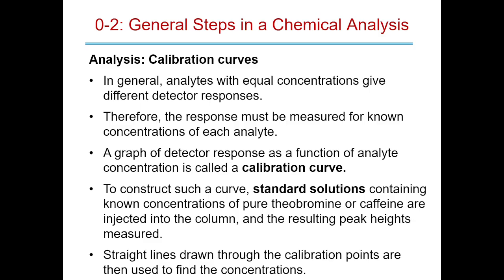By the way, you have to make new calibration curves for each instrument. You can't use one for one instrument on a different instrument, because every instrument will be a little different, right? Or maybe sometimes really different. So count on it. And don't count on it staying the same time-wise, okay? A good lab will do this over and over, like every day.